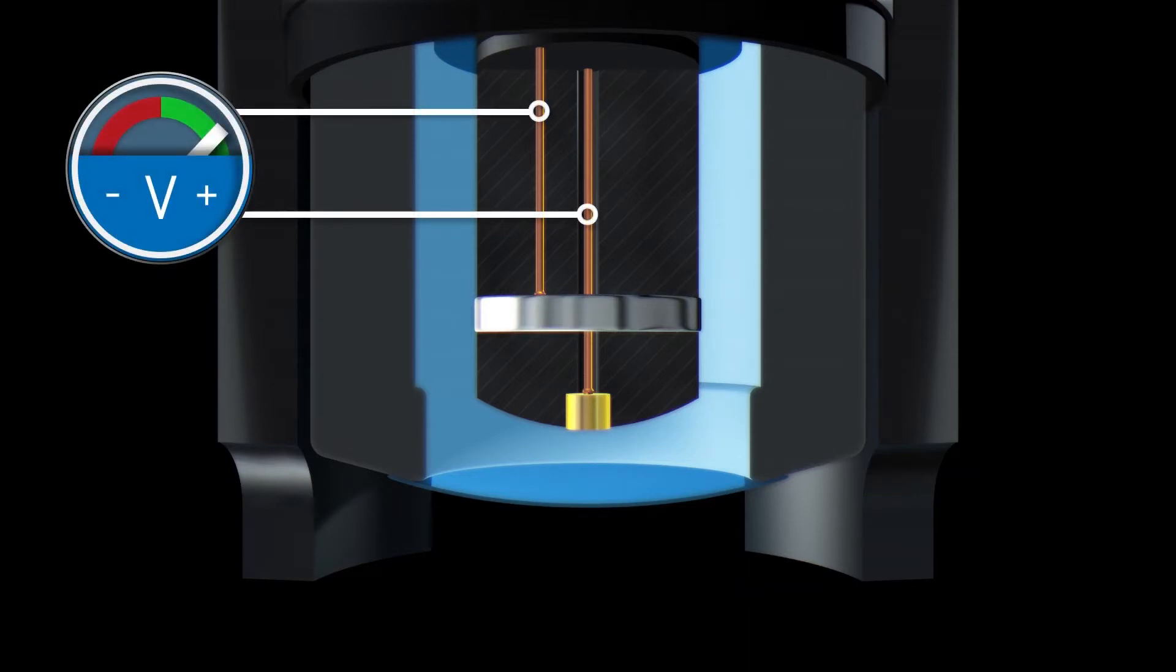The cathode and anode are located in a reaction chamber that is filled with an electrolyte. The reaction chamber is separated from the medium by a membrane. This porous membrane allows dissolved oxygen to diffuse into the sensor.